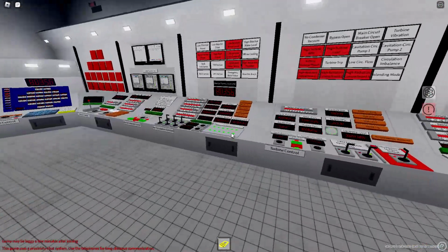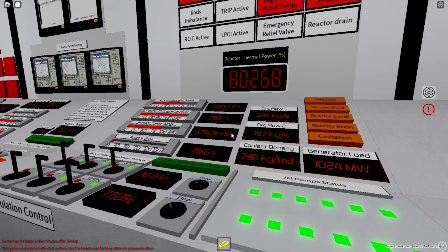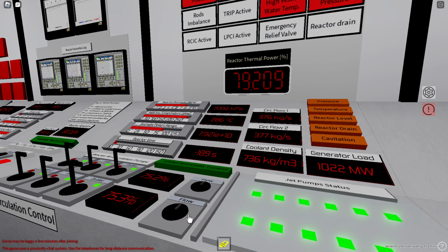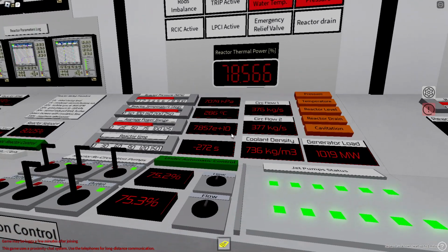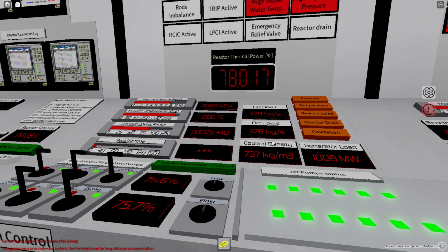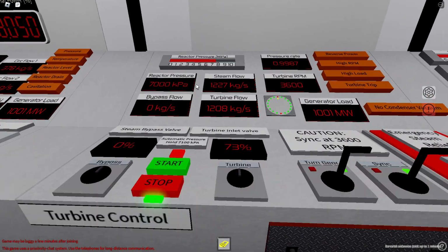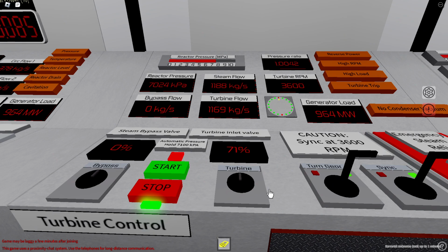Now the demand is slightly lower, here's what you can do: lower the thermal power with recirc slightly. I may have done a bit too much, so gently go down and increase it so it stops quicker. Now the reactor pressure is going down, so close a bit of turbine, but that reduces the generator load and increases the pressure, which increases the generator again. So you want to find the correct spot for the turbine valve.